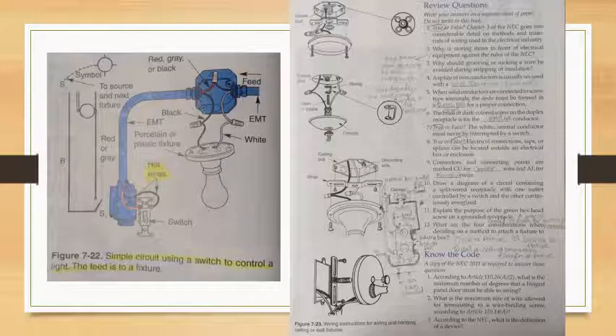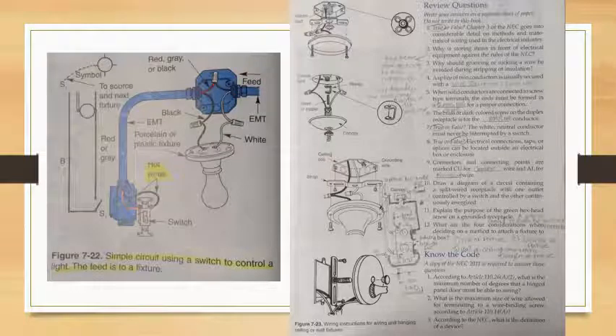Question 3. Why should grooving or nicking a wire be avoided during stripping of insulation? Because it may degrade the conducting qualities of the conductor and it may weaken the conductor to the point where it could break off and cause malfunctions in the circuit. Question 4. A splice of two conductors is usually secured with blank. Fill in the blank. That is a wire connector. Sometimes it's called a wire nut. Question 5. When solid conductors are connected to screw type terminals, the ends must be formed in a blank for a proper connection. Fill in the blank. And that would be a question mark shape. Question 6. The brass or dark colored screw in the duplex receptacle is for the blank conductor. That would be the hot or line conductor, or current carrying conductor.